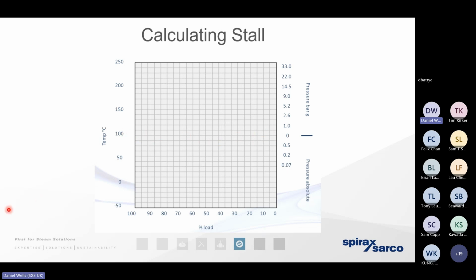So the first thing that we want to do when we're calculating the risk of stall occurring is we want to look at the process conditions. For example, if a heat exchanger's working at 100% load, it could potentially need to elevate water from 25 degrees to 75 degrees. If the water's coming onto the heat exchanger at 75 degrees, we don't need any steam. So that's dictated as being a 0% load. We plot the temperature and pressure from one side of the curve to the other.